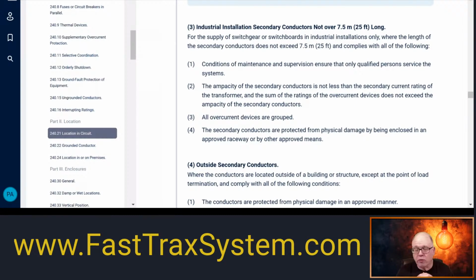Again, taking voltage drop, which is not a requirement, but taking those things into consideration. But once you meet those rules, because now you have the transformer protection as well as you are now following the secondary conductor rules for those 10-foot spans. Make sense? And so we will go over the 25-foot one and all those other types of things.